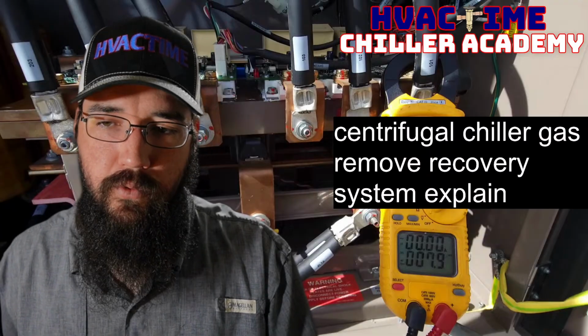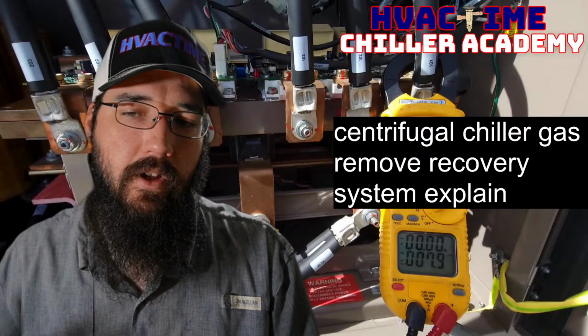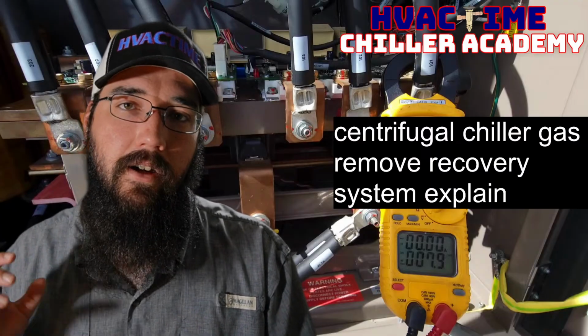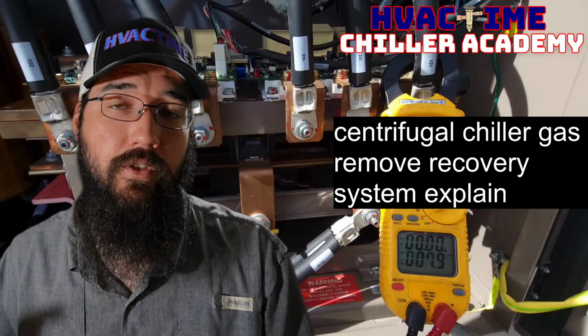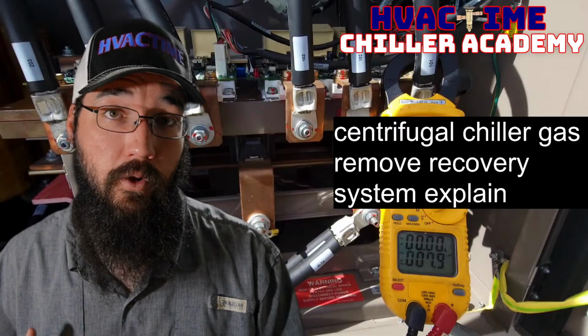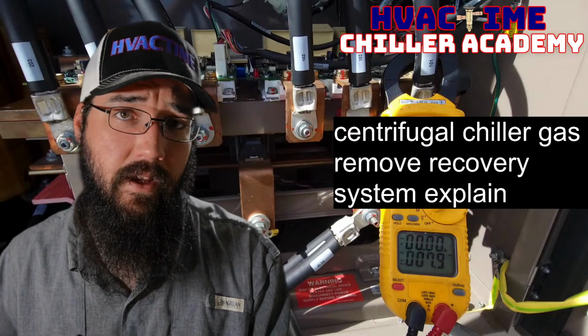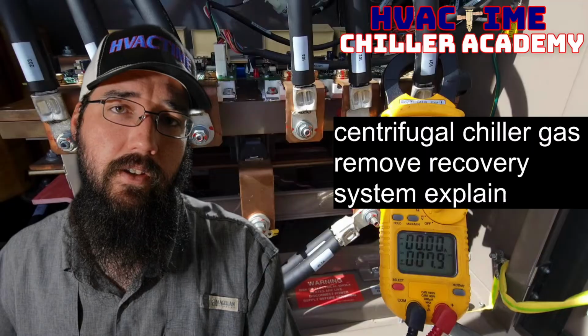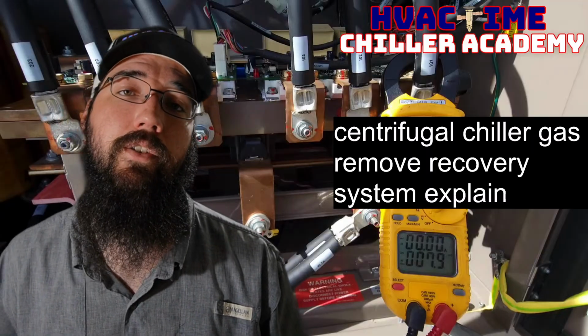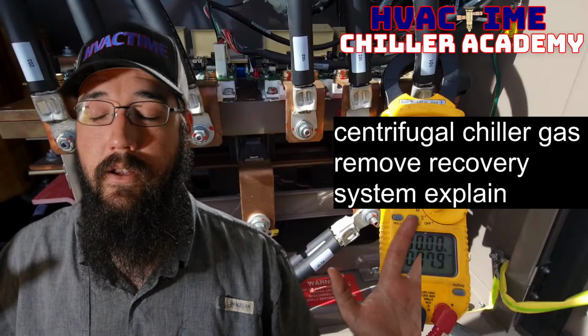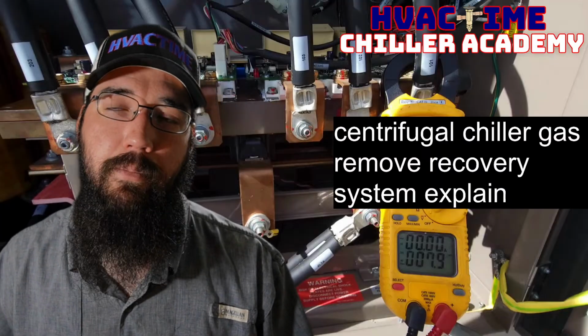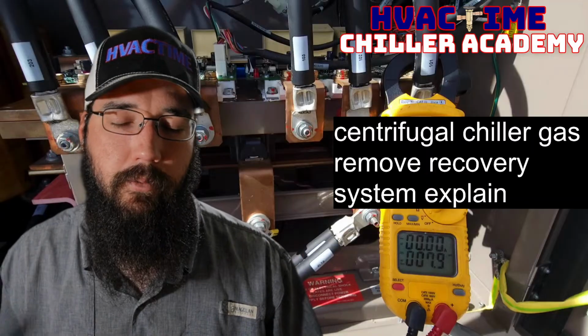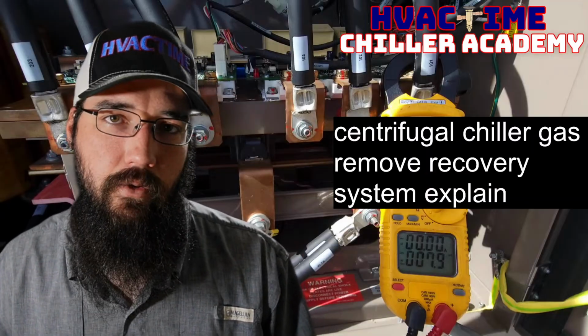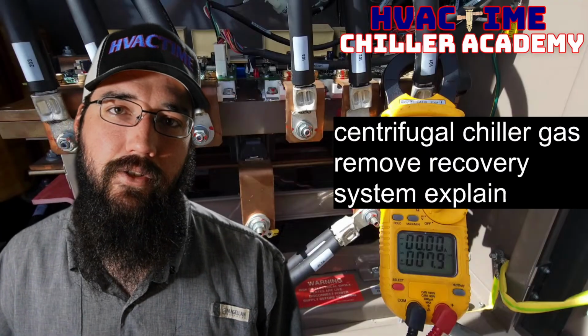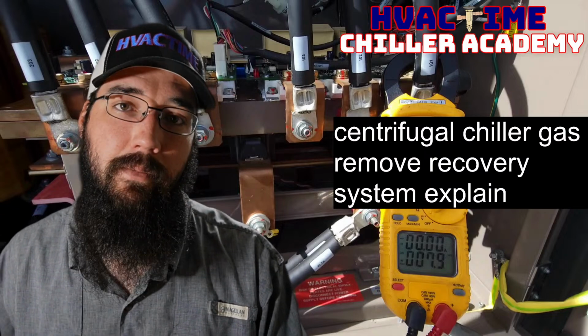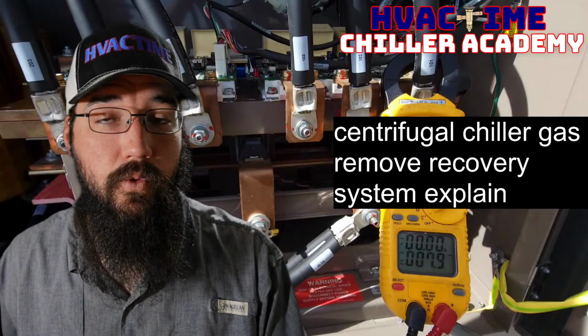Centrifugal chiller gas recovery system, explain. So we're just talking about the centrifugal chiller recovery process. I do have a set of service procedures in my service training program at chilleracademy.com where I go over this. I cover low pressure, I cover high pressure. I discuss it from a push-pull perspective, which is my recommendation. I also discuss it from a direct recovery perspective, if for some reason push-pull is not an option, which happens in some circumstances. Then you can implement an alternative, direct recovery, or standard recovery, instead of the push-pull route. All of that is in Chiller Academy under the service training program if you would like step-by-step guides of this process. Now, we'll do a quick overview of it.